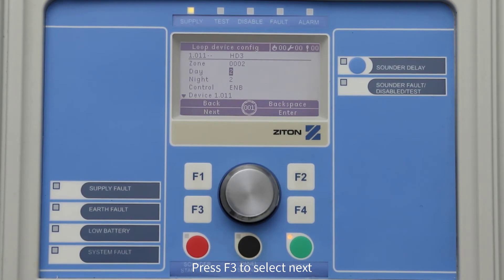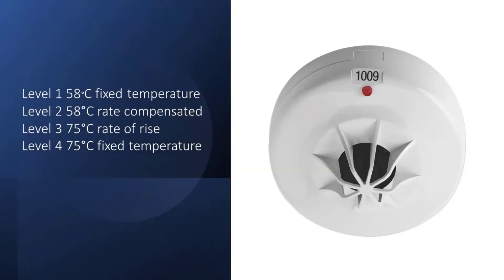This moves the cursor to the daytime sensitivity setting. For a heat detector there are four possible settings: number one will set the device to 58 degrees fixed temperature; number two will set the device to 58 degrees rate compensated; number three will set the device to 75 degrees rate of rise; number four is an additional option.